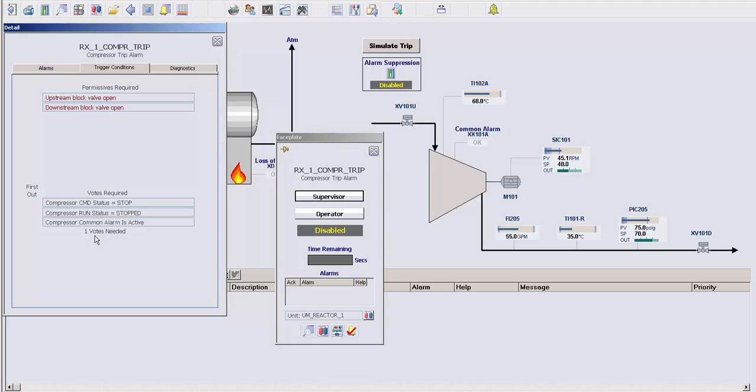But in this module, I have three conditions and one vote needed. So if one of these three conditions becomes active, the module will trigger the suppression of all the alarms. This can be configured with up to 16 conditions and as many votes as you like to trigger the suppression.